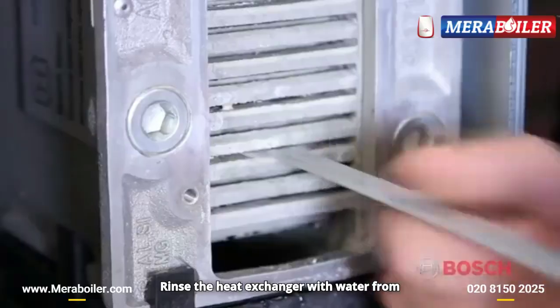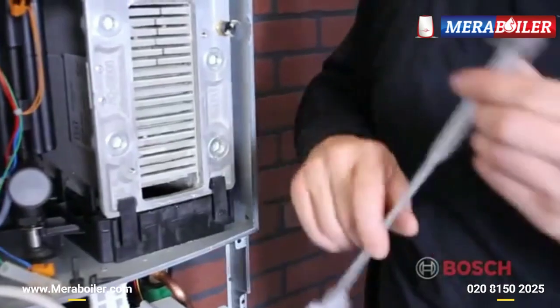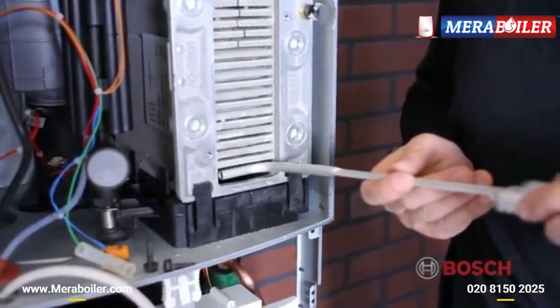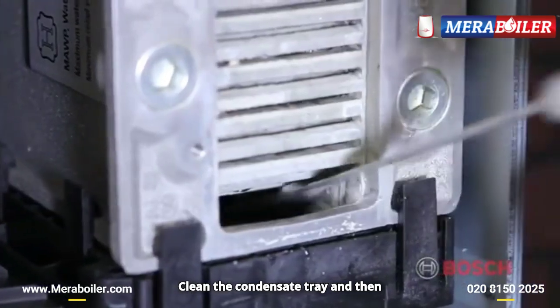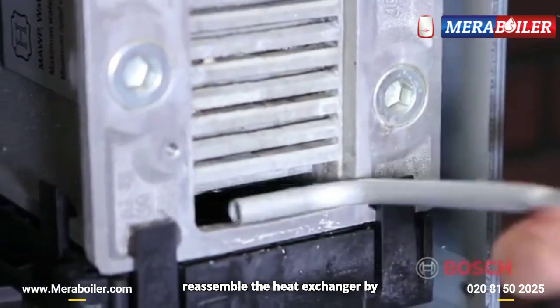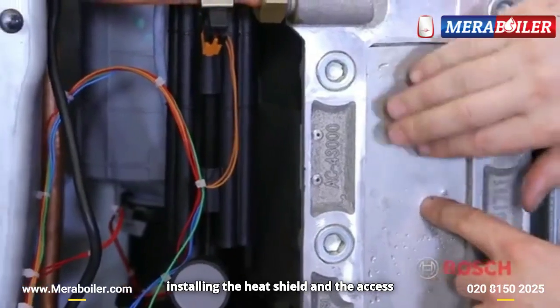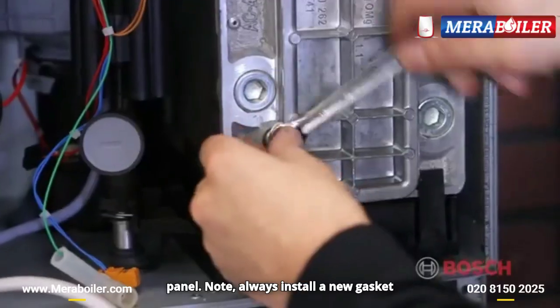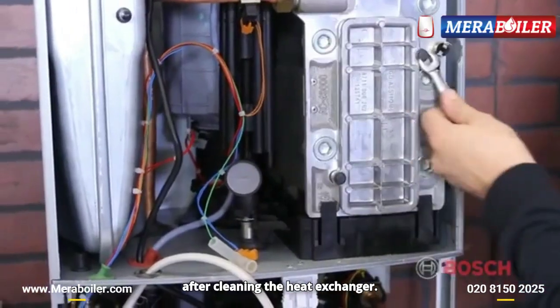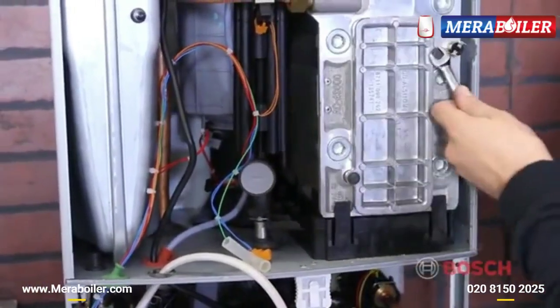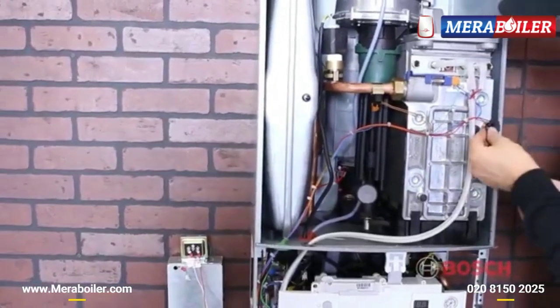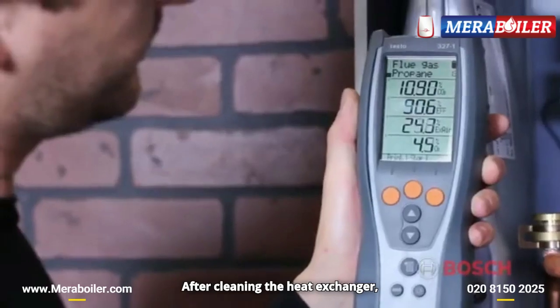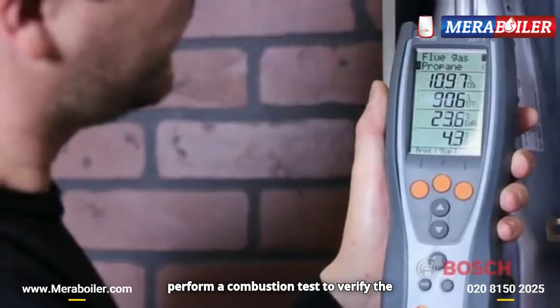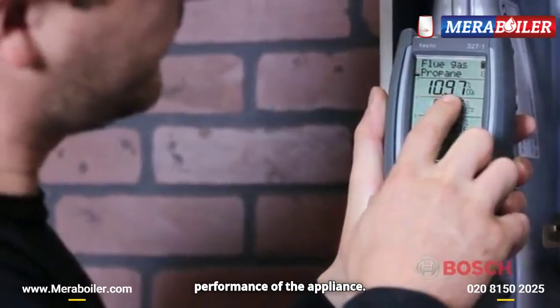Rinse the heat exchanger with water from the top. Clean the condensate tray and then reassemble the heat exchanger by installing the heat shield and the access panel. Note, always install a new gasket after cleaning the heat exchanger. After cleaning the heat exchanger, perform a combustion test to verify the performance of the appliance.